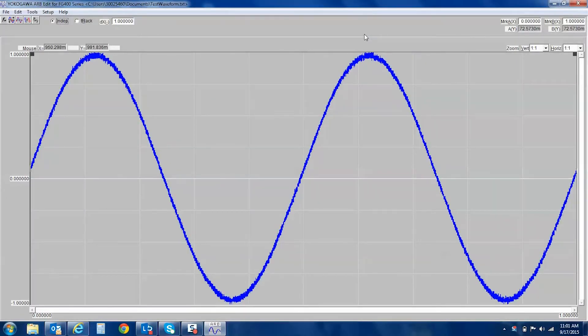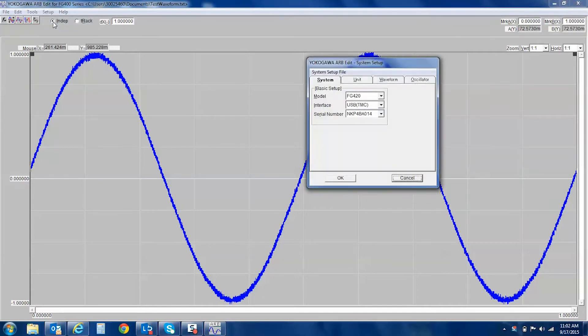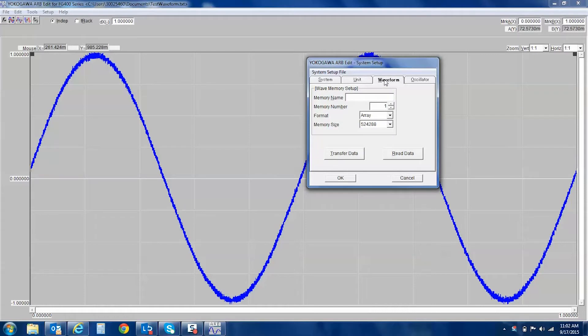Now that the file has been located and opened, you can see that this is indeed the waveform that was previously captured. By simply going into the Setup menu, selecting Setup, selecting the Waveform tab, adding a memory name, selecting a memory location, and simply pressing Transfer Data.